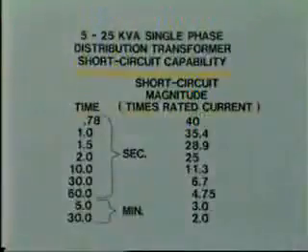But exactly how long can this fault current be tolerated? As you would expect, transformers will be able to withstand high magnitude fault currents for very short periods and relatively low magnitude fault currents for somewhat longer periods.